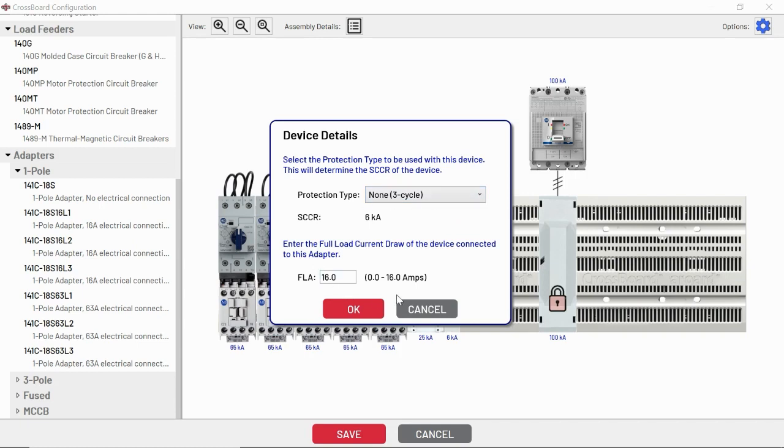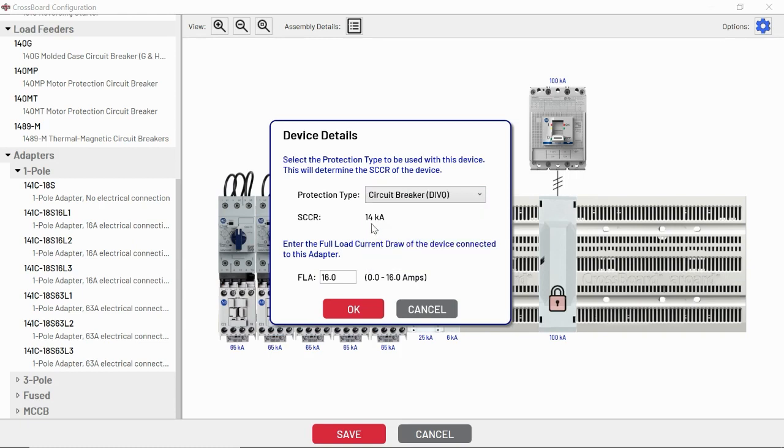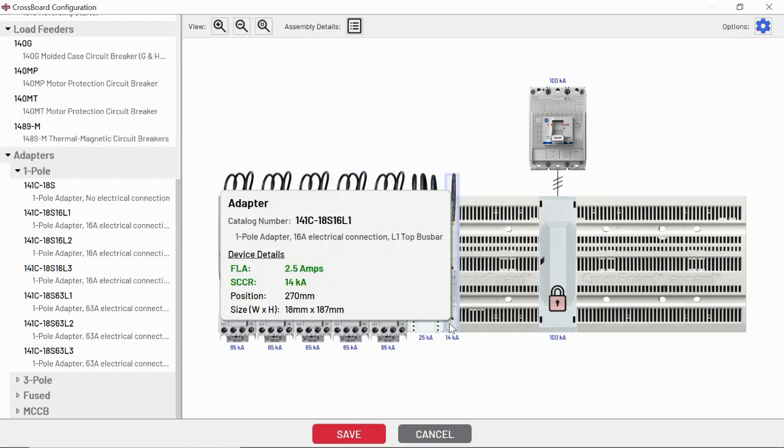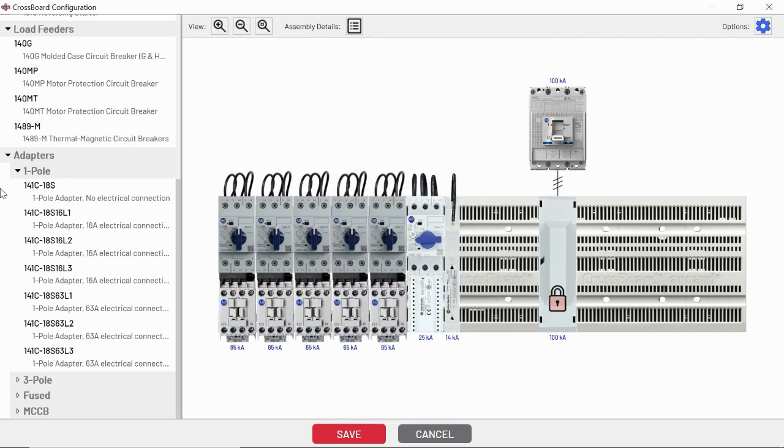When you're putting on just a blank adapter, it's going to ask you, what's your protection type? Let's say we have a one pole adapter on here. That's going to drive our SCCR rating. And again, this tool is keeping track of your FLA for you. You can just go ahead and put how much current you plan to draw off that phase. You'll see it's keeping track of our total current there for you.